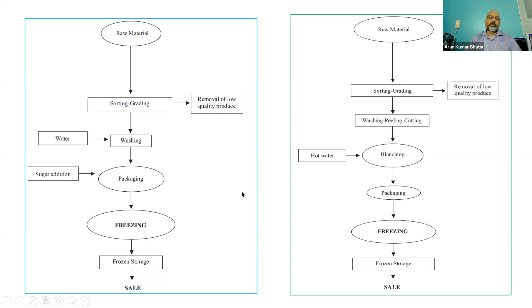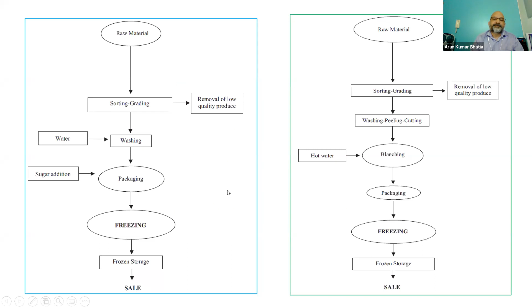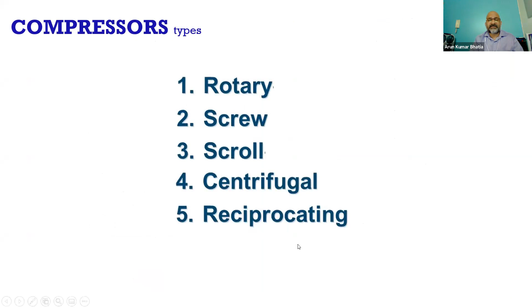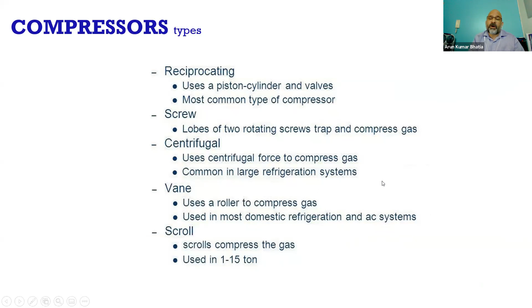Now coming to another mechanical engineering segment, the compressor. The next most important thing in any cold store is the compressor, which is the heart of the cold store. By principle there are 5 types: rotary, screw, scroll, centrifugal, and reciprocating. The most popular in cold stores is the reciprocating type, where we have a piston, similar to a car engine, with a piston and valve plate. Reciprocating, screw, centrifugal, and vane types are mostly used in air conditioning systems or smaller applications. I haven't seen vane type compressors in cold stores, but reciprocating, screw, and scroll I have seen. Centrifugal compressors are also not very popular in cold stores.